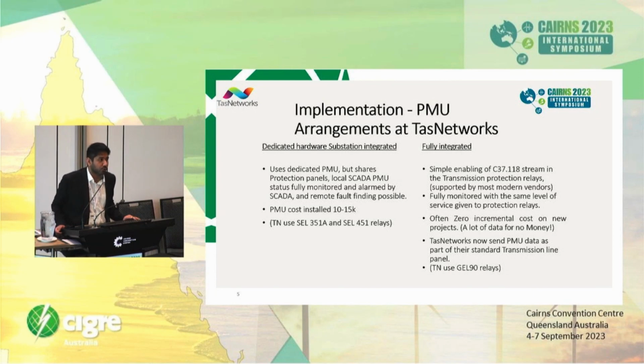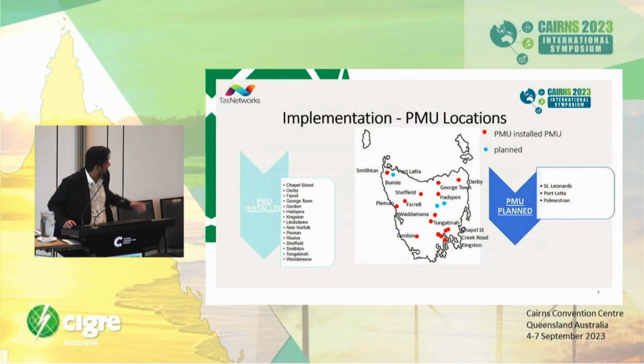Probably all the vendors support this stream. Currently we are using GE L90, and we have confirmed Siemens has this functionality as well. The classes are configurable, so you can do M class and P class. In our network we are doing P class, which is faster. It's a protection class PMU, while M is a measurement class, which gives you higher resolution. I'll just clip over this slide because of the shortage of time. That's the Tasmanian map. The red dots show the installation of PMUs in our network, while the blue dots are the ones where we have planned installations.